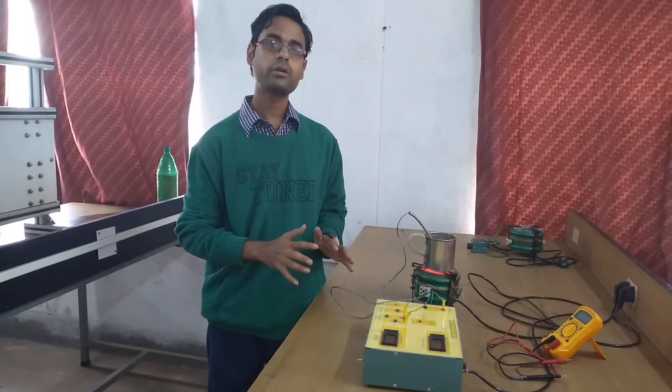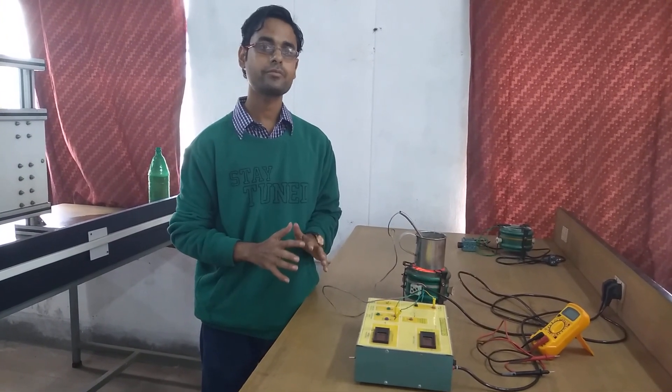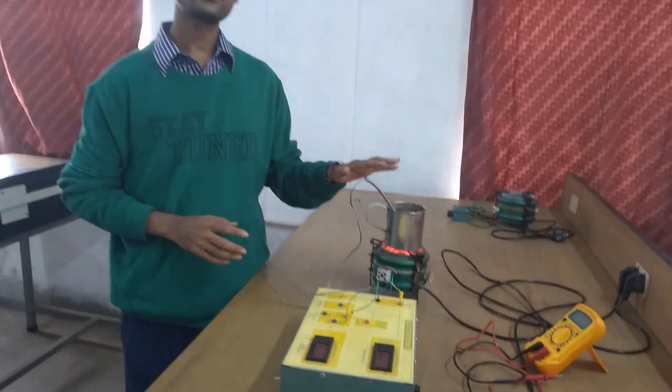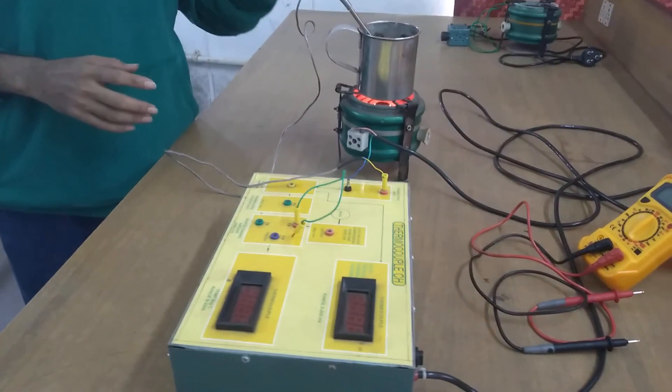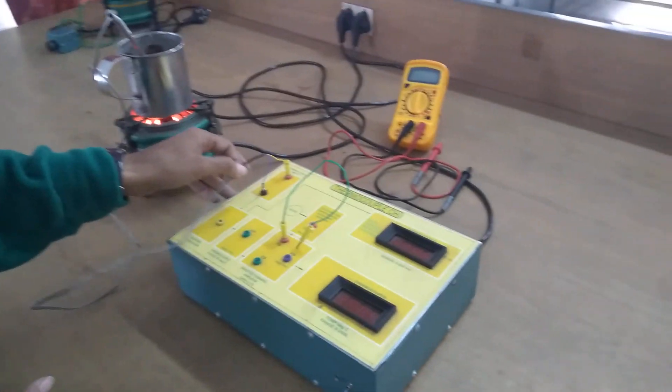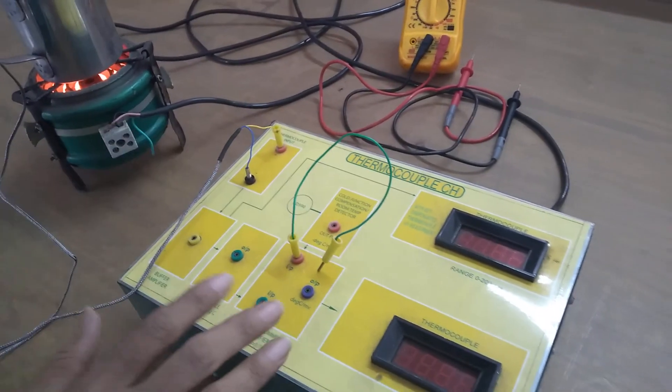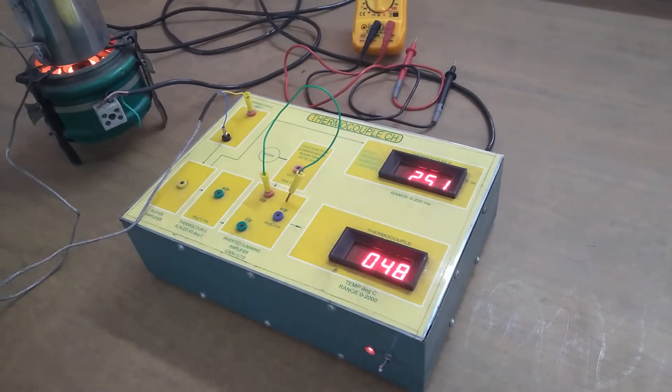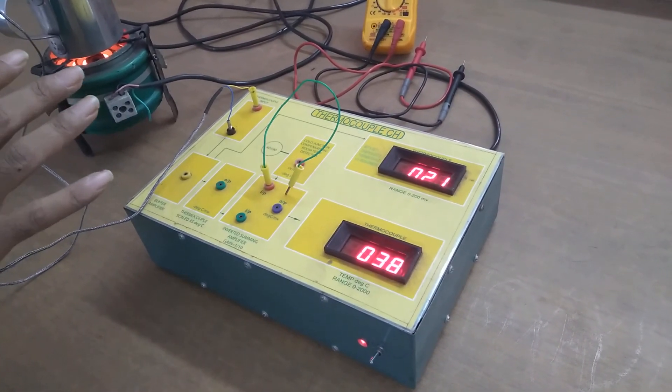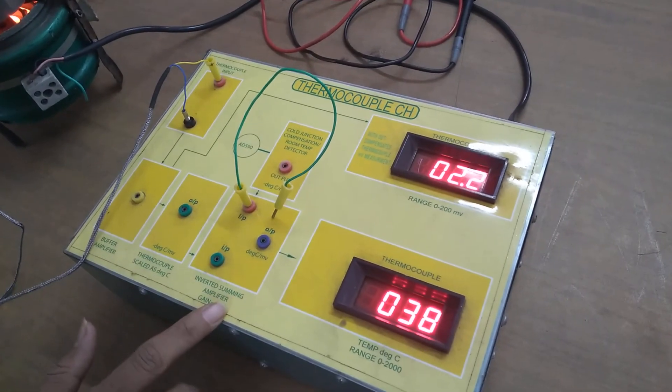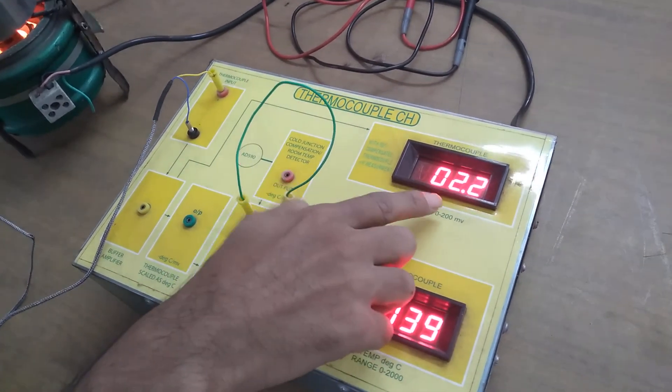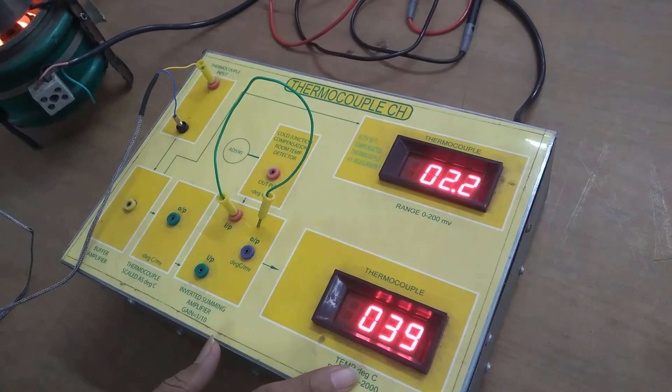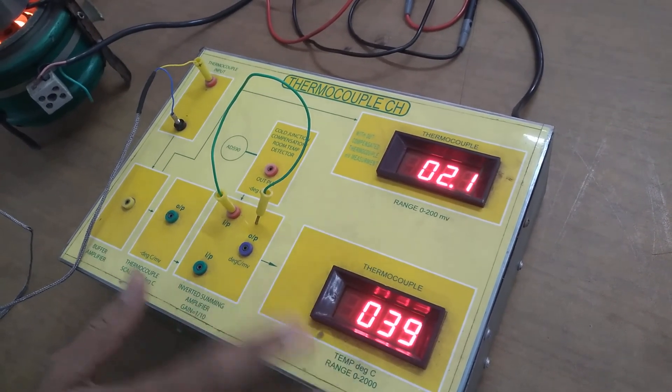So this time around we are going to look at the thermocouple trainer kit for conducting this experiment. For that purpose we have placed our thermocouple at process temperature and we have connected the two leads to these two ends of the thermocouple trainer kit. And if we turn on this trainer kit without cold junction compensation, what you find is that the thermocouple provides a millivolt of 2.3 and the corresponding temperature is around 39 degree centigrade. This is uncompensated.